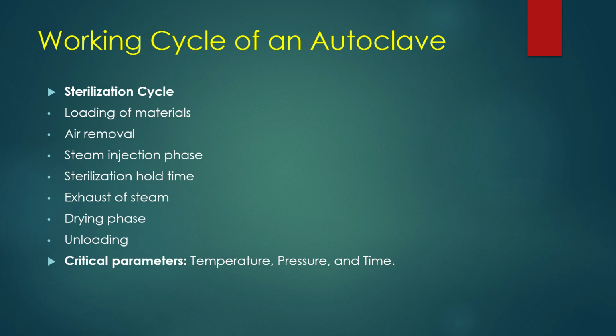Let's see step-by-step working cycle of an autoclave. The autoclave sterilization cycle begins with loading the material, followed by air removal to ensure effective steam penetration. Saturated steam is then injected and the load is held at the required temperature, pressure and time to achieve complete sterilization. After the exposure period, the steam is exhausted. The load undergoes a drying phase and the sterilized materials are finally unloaded. Critical process parameters: the effectiveness of the sterilization cycle depends on maintaining the correct temperature, pressure and exposure time throughout the process.